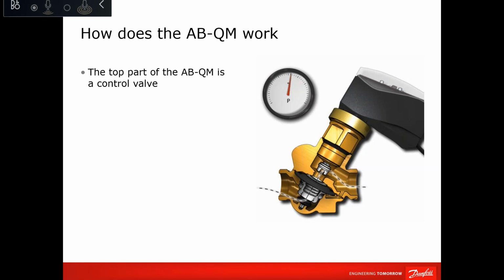Another important advantage which we need to talk about is the capability to change the control characteristic. If you have a mechanically equal percentage valve, there is a high chance that this characteristic might be affected by the system hysteresis, as they call it, because the valve will be vibrating internally due to the proportional band, and it might open and close at a level of plus or minus 10 to 15% during the curve, but the curve will look like equal percentage. In our case, it's a software-based equal percentage characteristic, and that makes the valve a perfect equal percentage or linear based on the application.